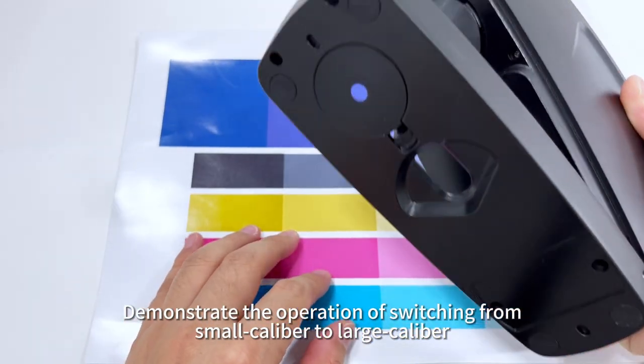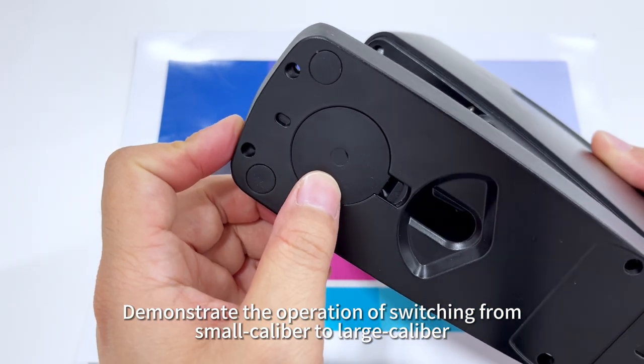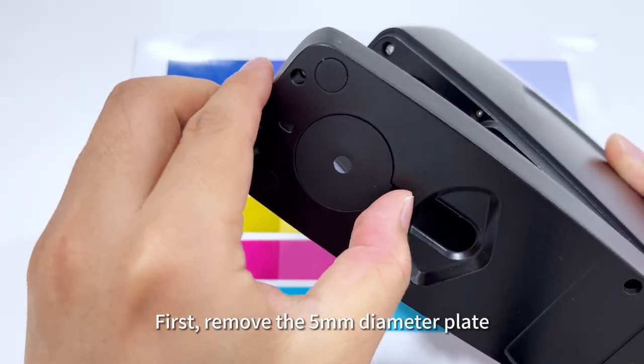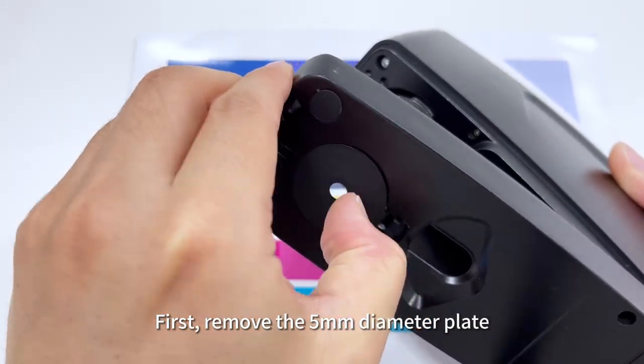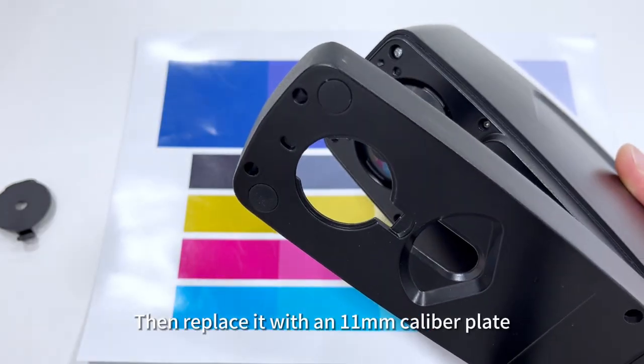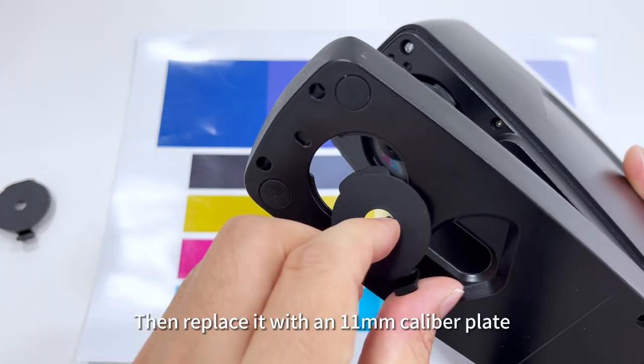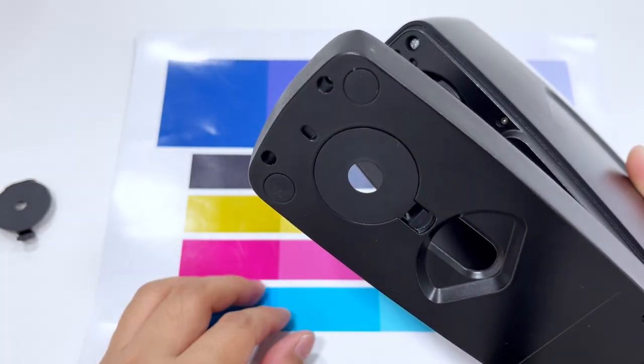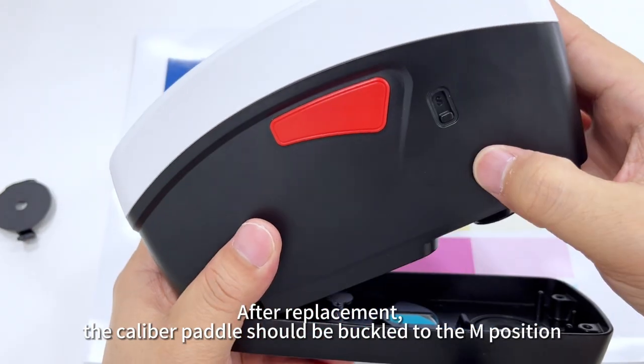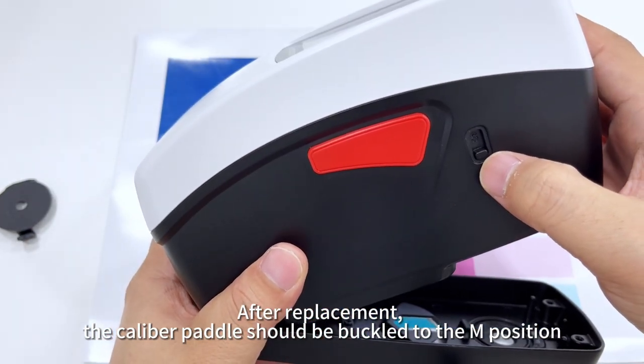How to switch caliber. Demonstrate the operation of switching from small caliber to large caliber. First, remove the 5 mm diameter plate. Then replace it with an 11 mm caliber plate. After replacement, the caliber paddle should be buckled to the M position.